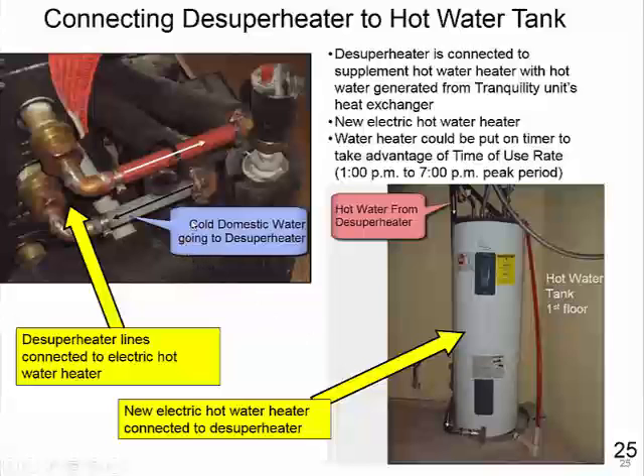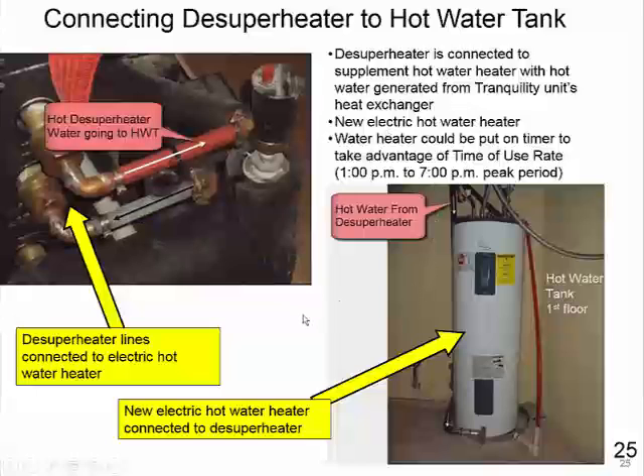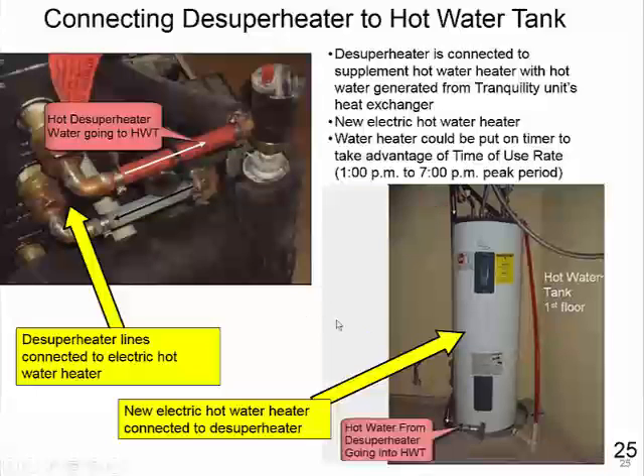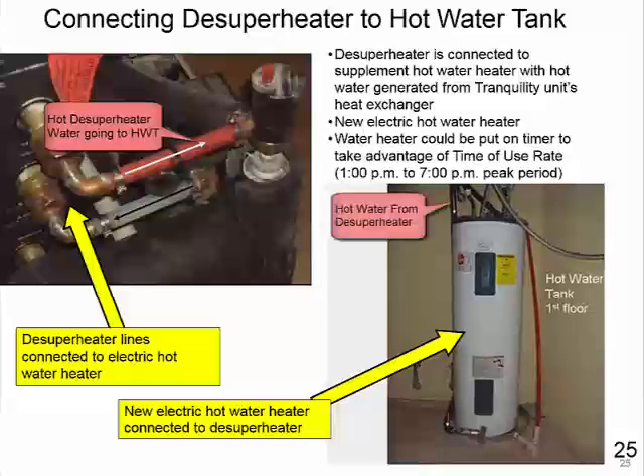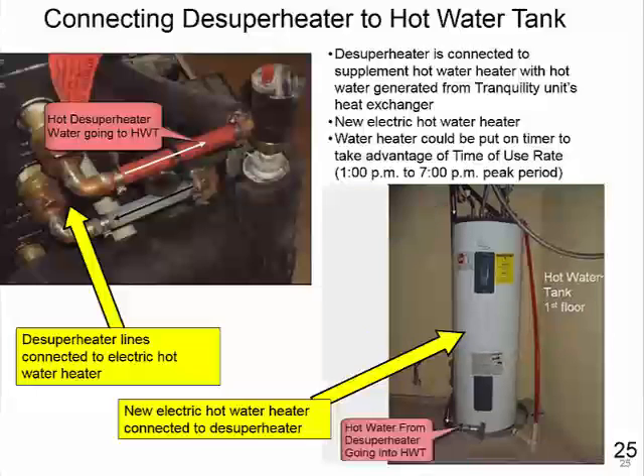Here you see the connection of the de-superheater to the hot water tank, and this is the de-superheater coming from the hot water tank. This is coming from the heat pump going to the hot water tank, and this is the domestic cold water coming in. And this was a 50-gallon electric hot water tank that I used. You can see the connection at the bottom going into the hot water tank. You see the hot water from the de-superheater is coming in there.